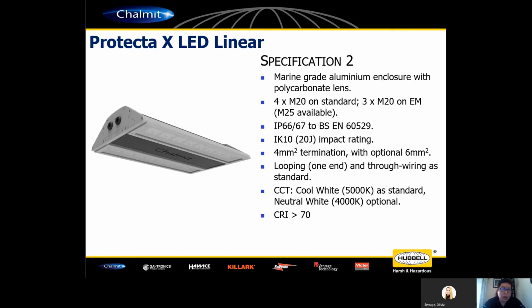As is standard for most of our product ranges, we can achieve an IP66, IP67 rating to the EN 60529 standard, and also an IK10 impact rating, the maximum IK rating available - a maximum impact of 20 joules. Bear in mind though that IK ratings are based on an impact test with the luminaire unconditioned. For all hazardous area products, they must also be impact tested after conditioning, typically 4 joules and 7 joules depending on where on the product - that's after the product has been aged, so a worst case essentially.